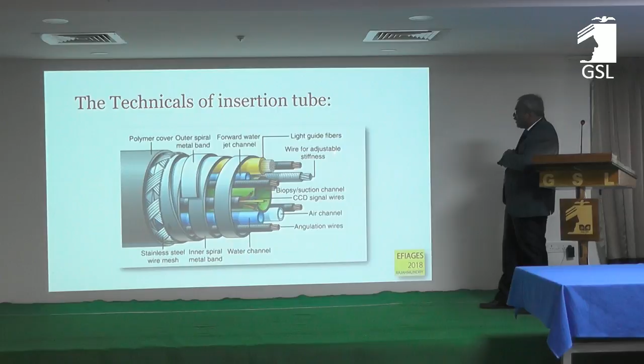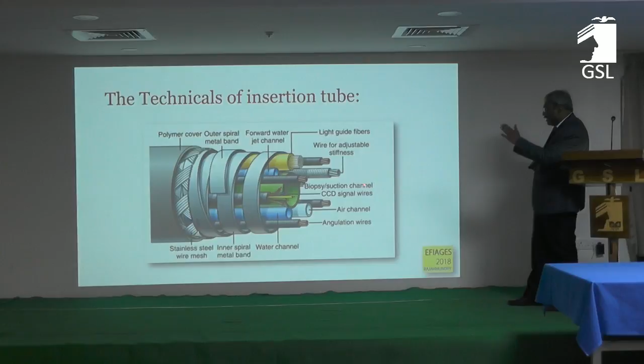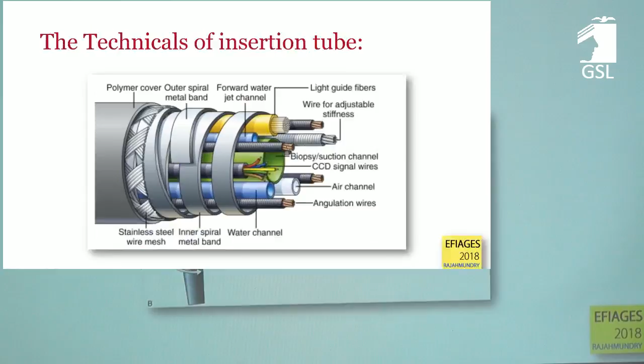So you see the water jet channel, light guide fibers, this wire for adjustable stiffness, you have the biopsy and the suction channel which is shared together, you have the charge coupled device signal wires, and you have the air channel, and of course we have 4 angulation wires for up and down, right and left. All right. So with this background of the technicals, we go now into the movements. I think you demonstrated the movements, it's fine. So how it works is something very fascinating.